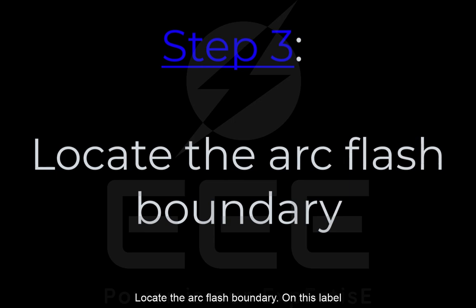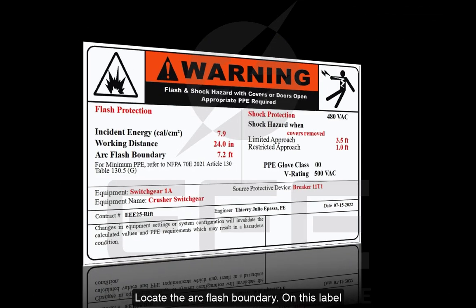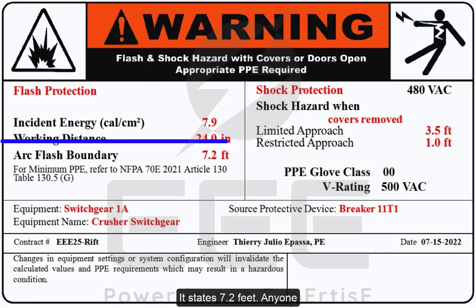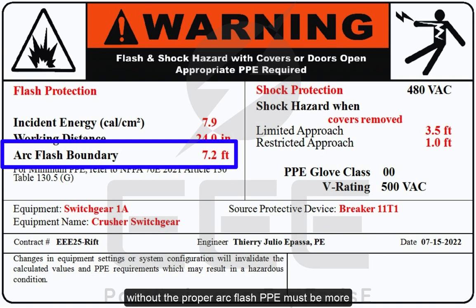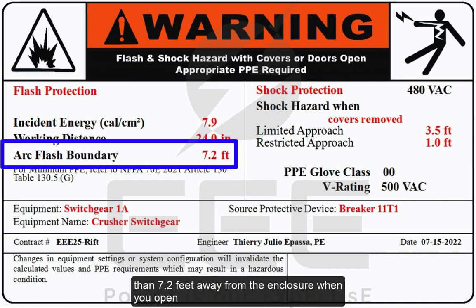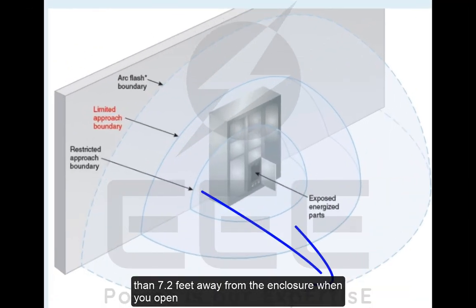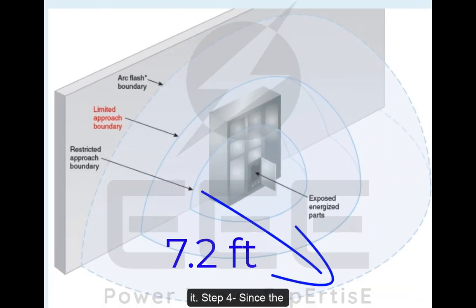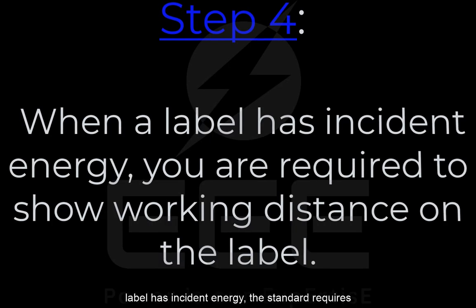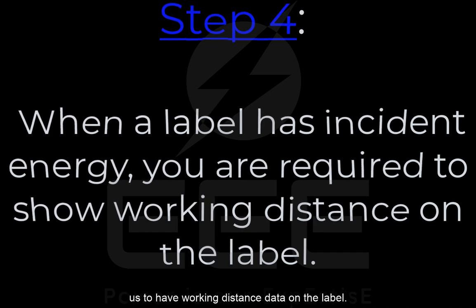Step 3. Locate the arc flash boundary. On this label, it states 7.2 feet. Anyone without the proper arc flash PPE must be more than 7.2 feet away from the enclosure when you open it.